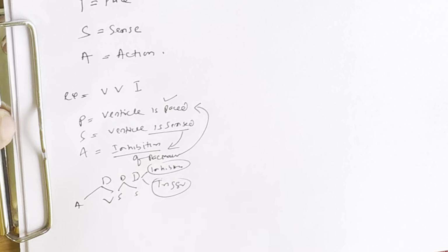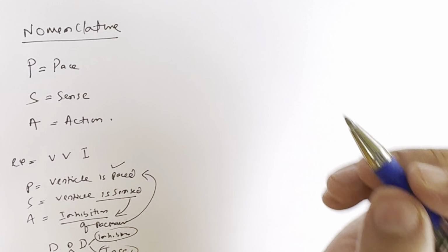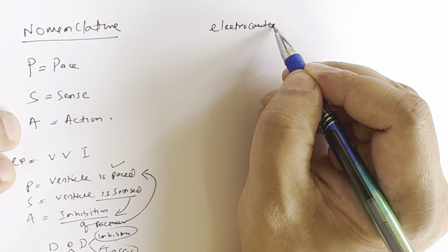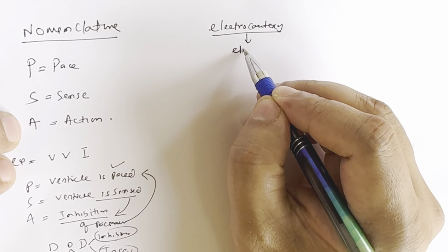Now there is a frequent thing you will hear while a patient is going to OT. The cardiologist is called, the pacemaker company is called to change the settings before the patient goes to ICU. Why does that happen? Let us discuss. Because in the operation theatre we use electrocautery.